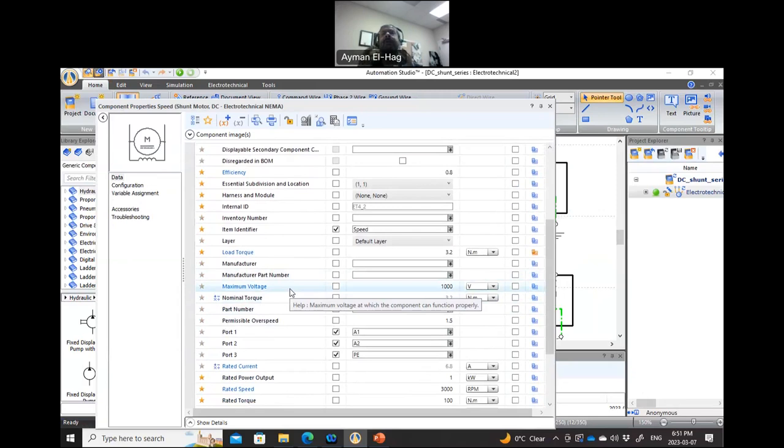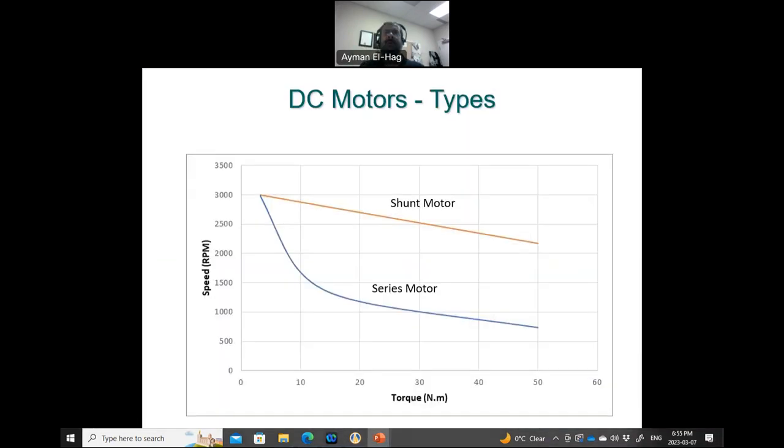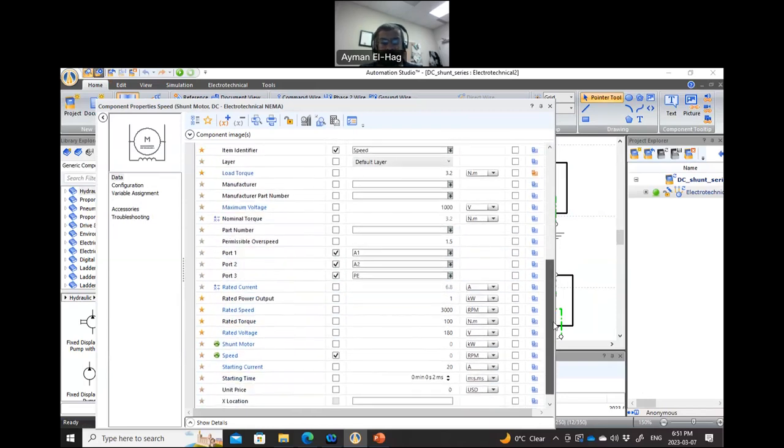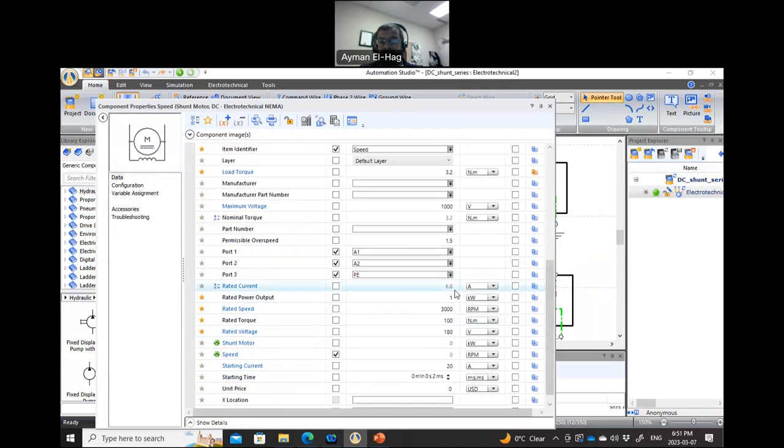So for this machine, it's 3.2 Newton meter. There is the rated current: 6.8 amp. When you work at no load, this is the current that you will have. The rated speed or the no-load speed is around 3,000 RPM. The rated torque, the maximum torque you can apply is 100 Newton meter, and your rated voltage is 180 volt.